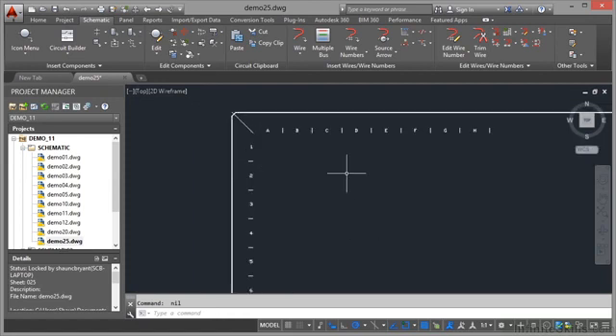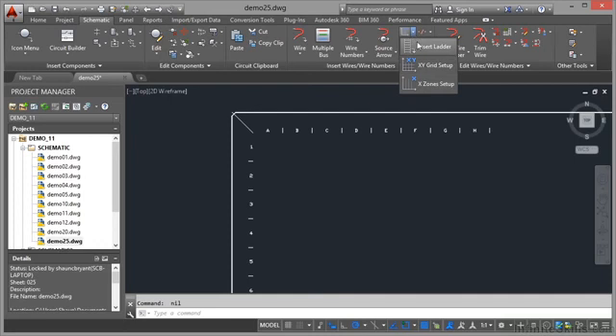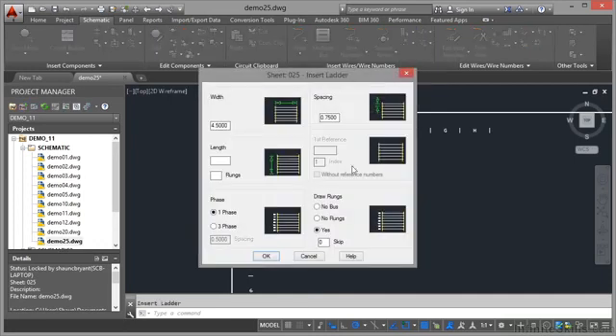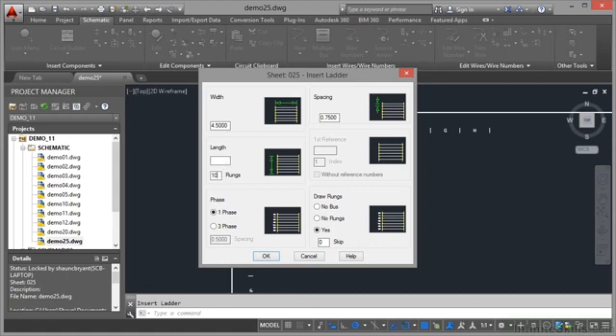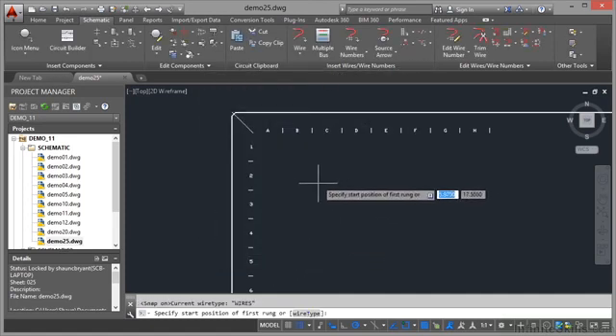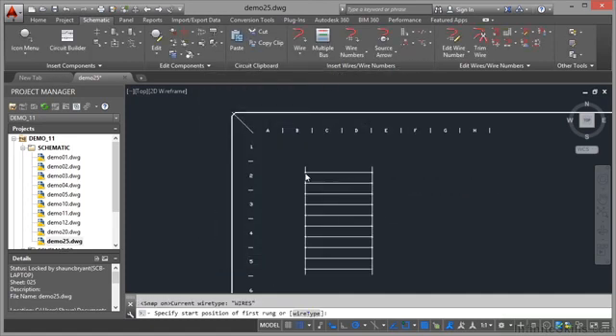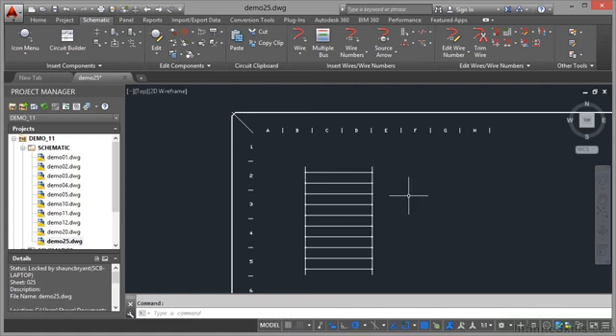So what happens now if I place a ladder? Can I place a ladder in a drawing that uses an XY grid? Well let's go and have a look. Insert ladder, I can still insert a ladder no problem. Width is 4.5, spacing 0.75, and let's go for I don't know, let's say 10 rungs, press tab that'll work that out for me. I'll leave it as one phase and draw the rungs yes, click on OK, specify a start position say there. And you'll notice this time there are no reference numbers on the actual ladder itself.